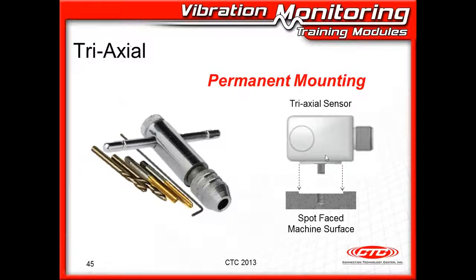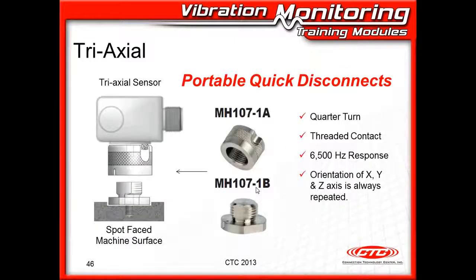Looking at our triaxial sensor, again, we do have a foot on this. It's a little more forgiving. You might get about 3 millimeters here. So again, we're going to bring that down into our spot face for permanent mounting, and put that right in position there. Also note that when you're permanently mounting a triax, it's up to you to orient the axis in the correct directions.